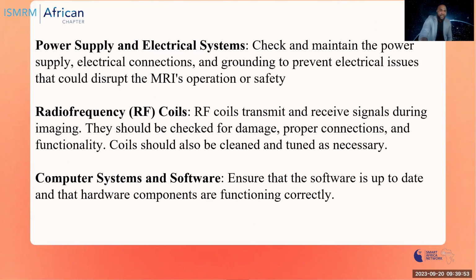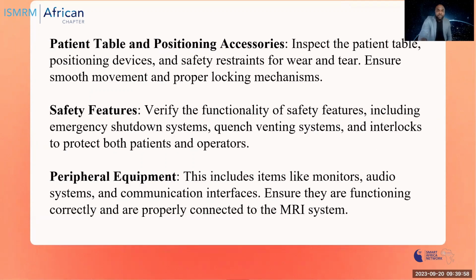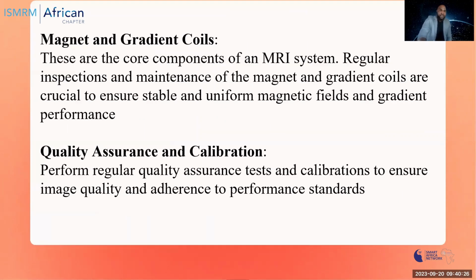Computer systems and hardware, the console, the monitor must be checked and also serviced. The patient table must be checked. You check the motor, ensure that the motor is working well, and also the accessories. All safety measures must be put in place. From the door side of the MRI, the supervised area, ensure that there are warning labels to let people know that they are entering a high superconducting environment. Then the peripheral equipment and accessories also have to be checked and maintained.